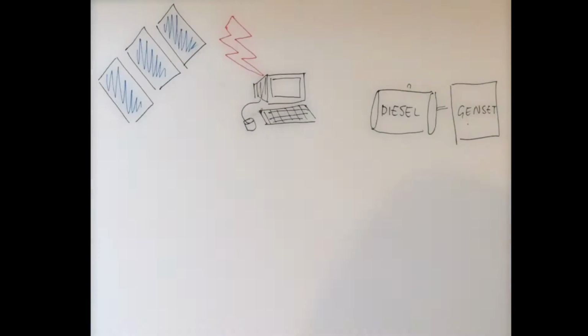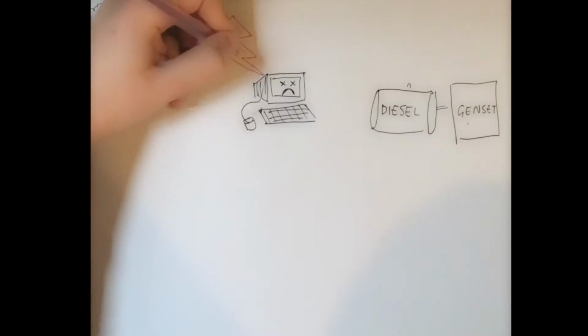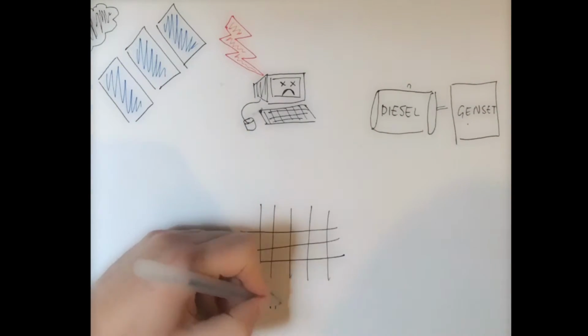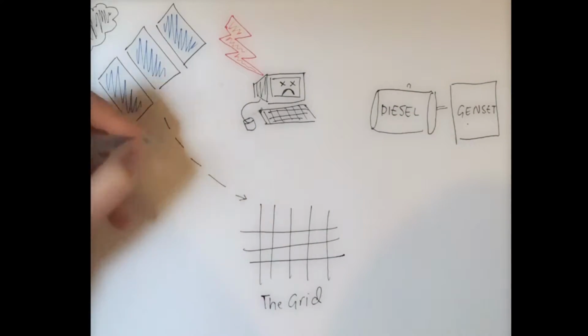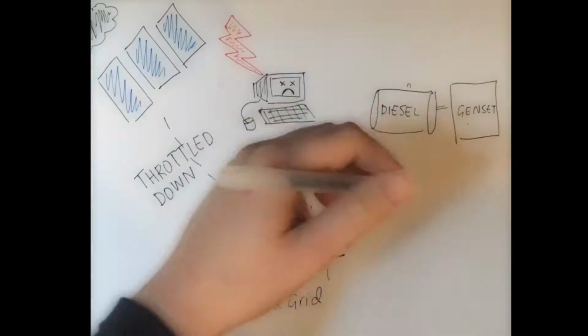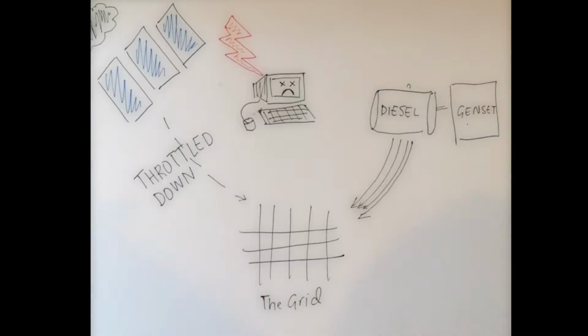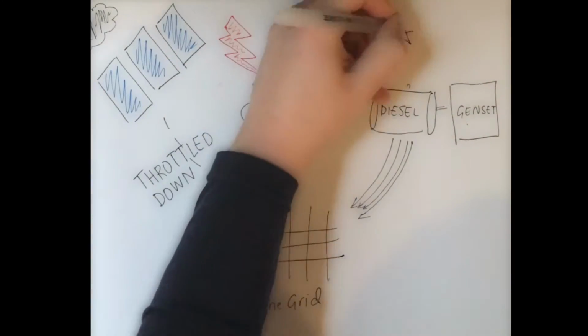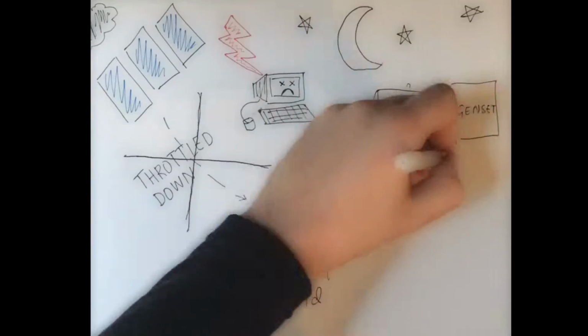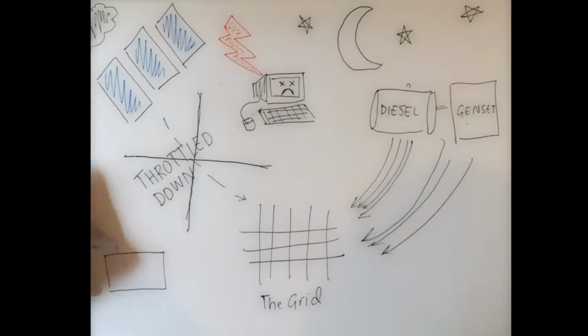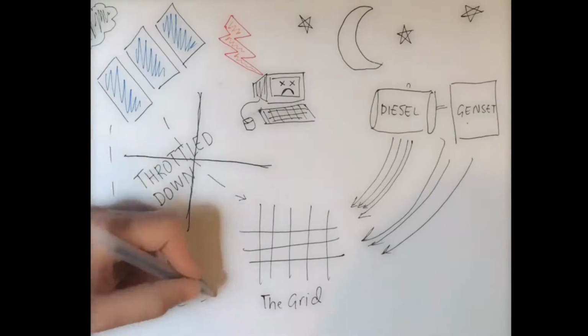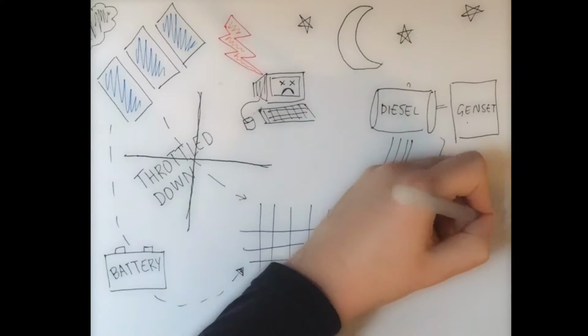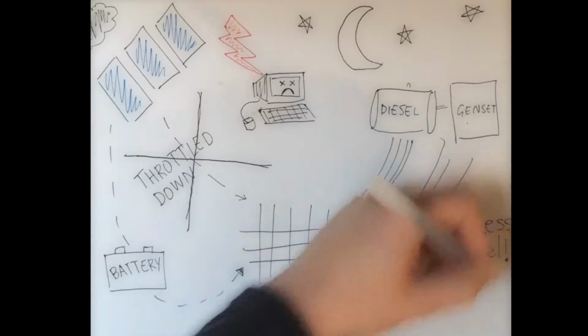If sudden load changes occur, the hybrid system reacts quickly. If necessary, photovoltaic power is throttled down to guarantee smooth genset operation and optimum grid stability. In the evenings, gensets take on more and more energy until the night when they take the entire load. If you use battery energy storage, you can save up to 10% more fuel.